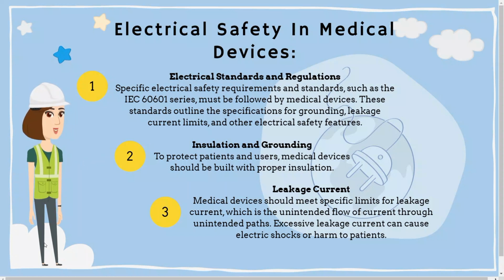Specific electrical safety requirements and standards, such as the IEC 60601 series, must be followed by medical devices. These standards outline the specifications for grounding, leakage current limits, and other electrical safety features. Secondly, insulation and grounding. Medical devices should be built with proper insulation. Thirdly, leakage current. Medical devices should meet specific limits for leakage current, which is the unintended flow of current through unintended paths.